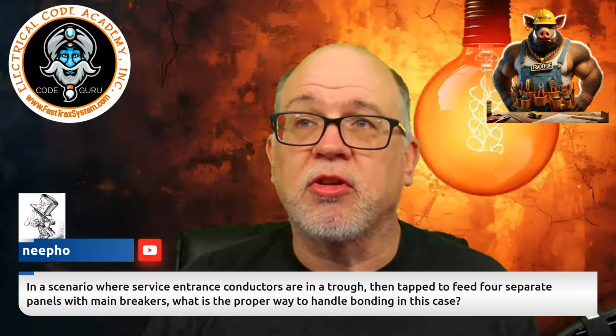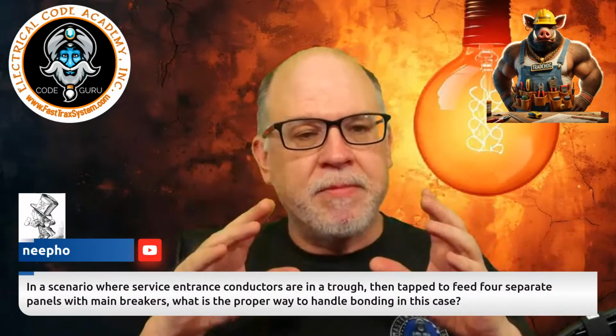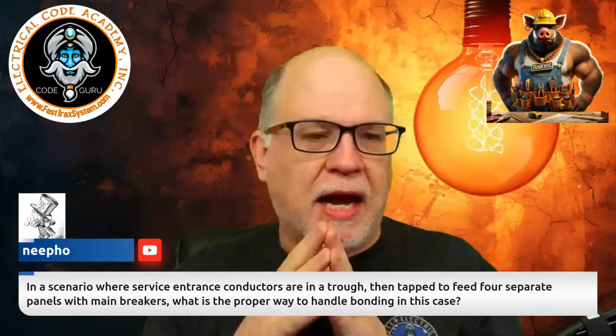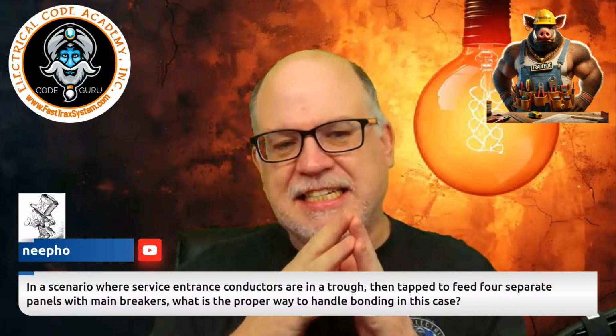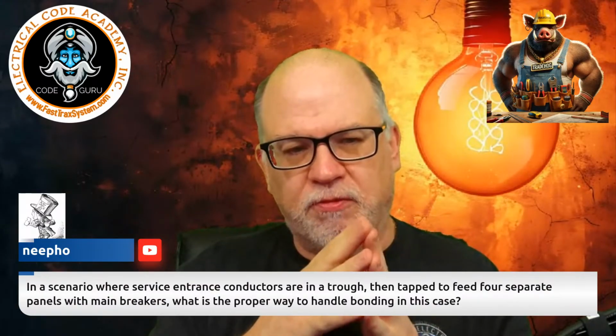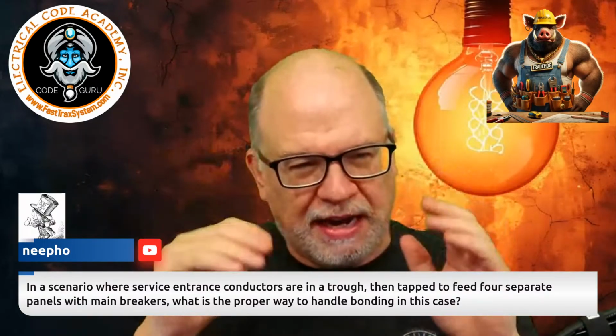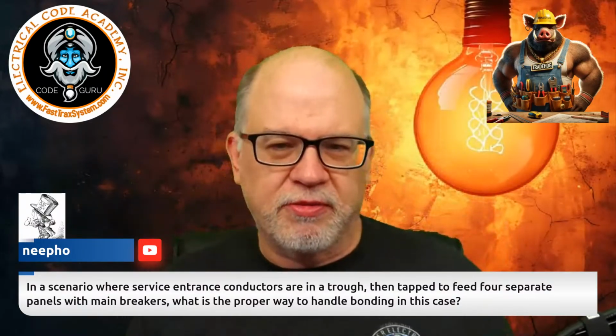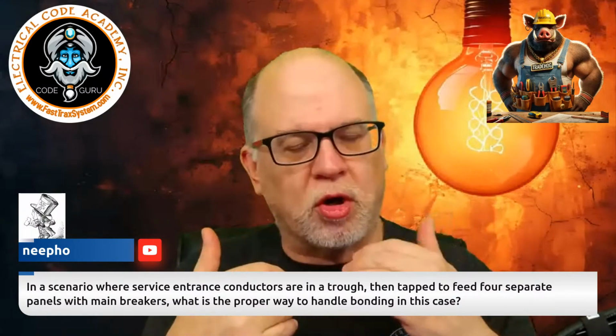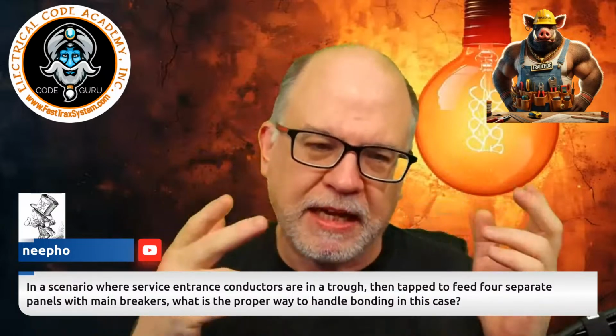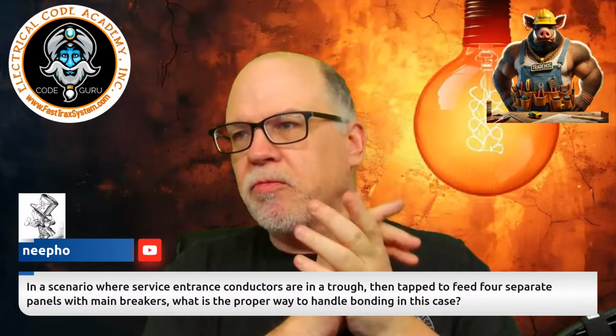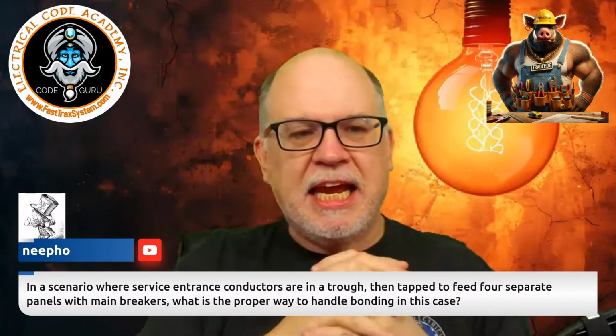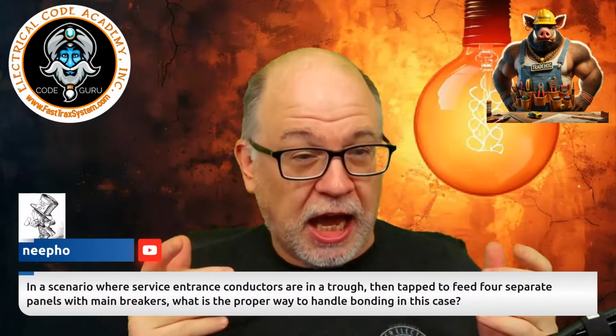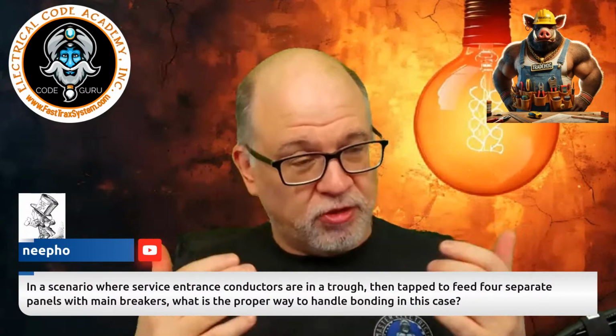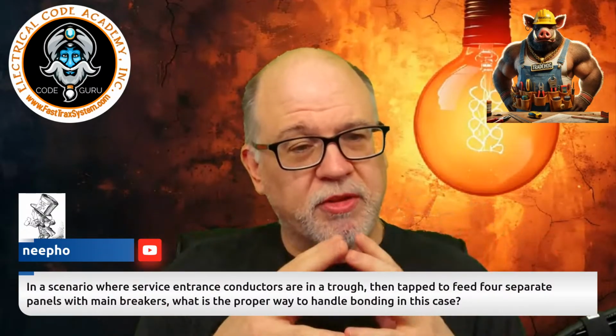Another way is obviously making sure you follow all of the bonding requirements in 250.92. Make sure you check 250.92, because you have those different types of methods to do what's called assured bonding. You can't use standard lock nuts, you have to do something a little more when it comes to bonding.